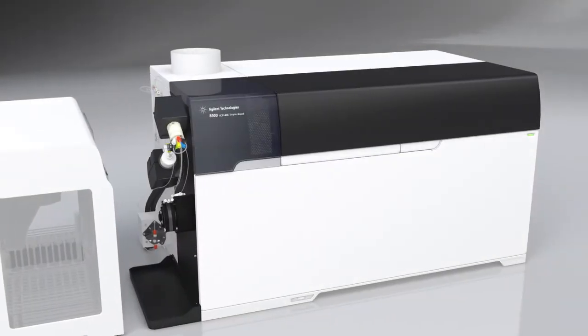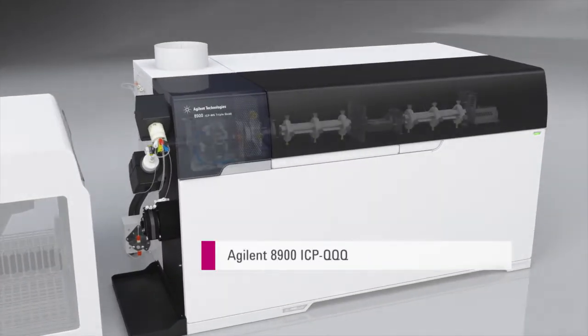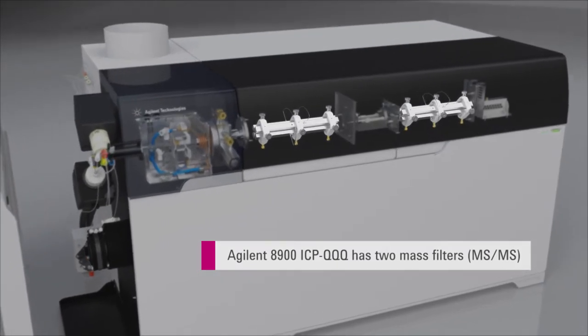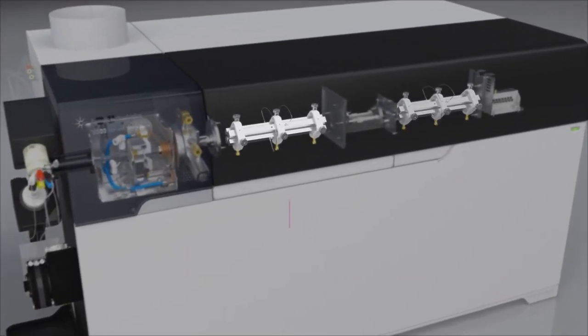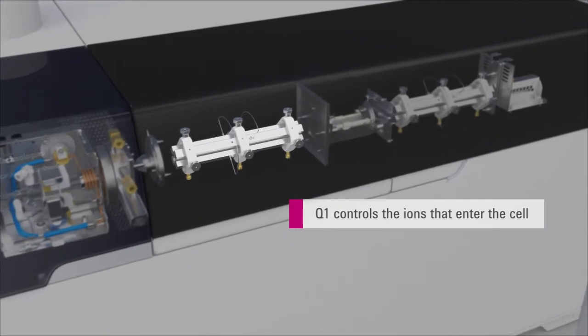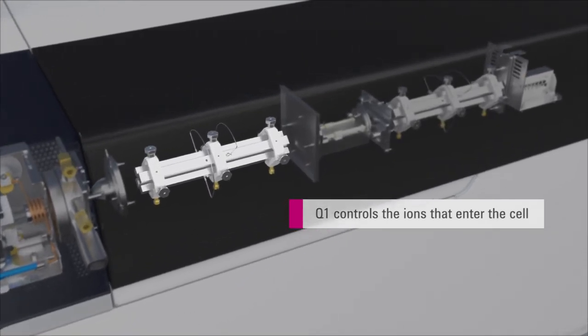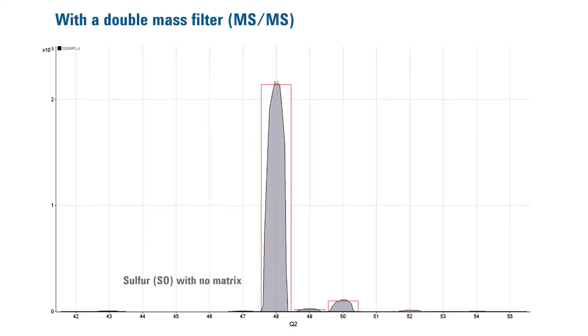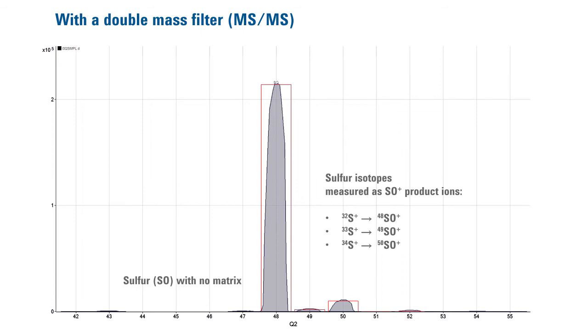The new Agilent 8900 ICP triple-quad provides the solution. The 8900's tandem mass spectrometer configuration uses an additional quadrupole mass filter, Q1, placed before the cell. In MS-MS operation, Q1 controls the ions that can enter the cell. The same reaction chemistry is used, but Q1 controls the target sulfur isotope that can enter the cell.